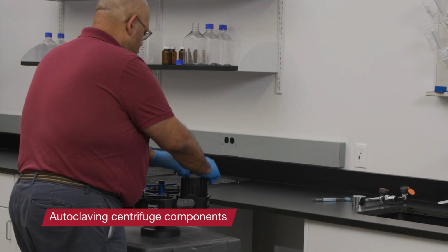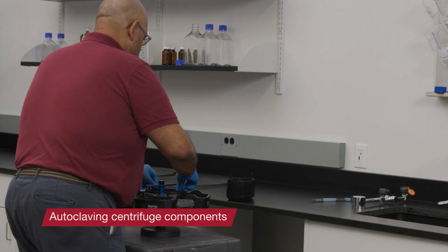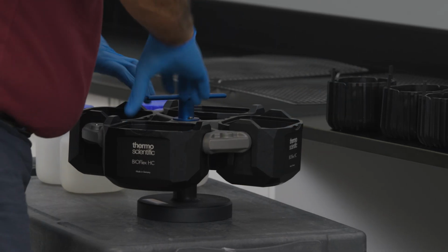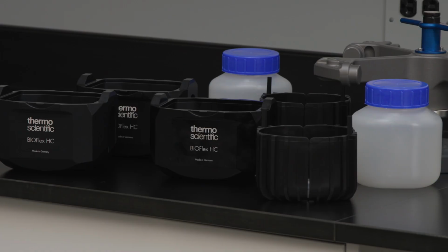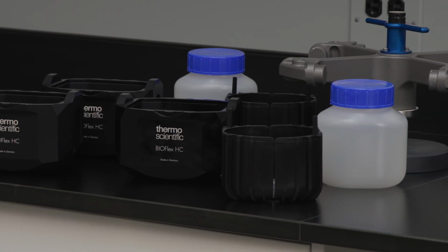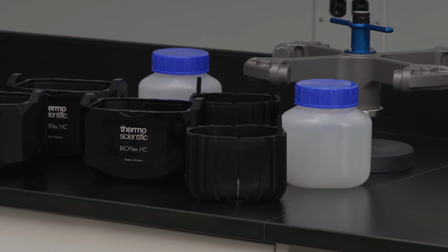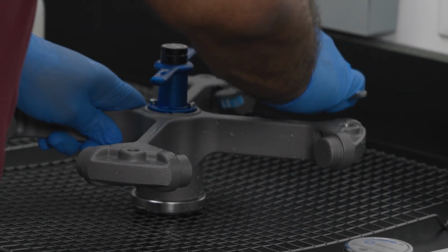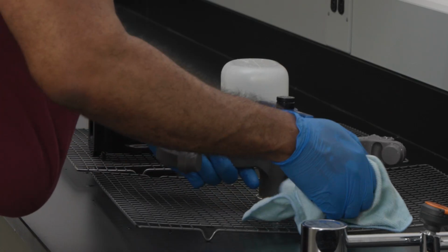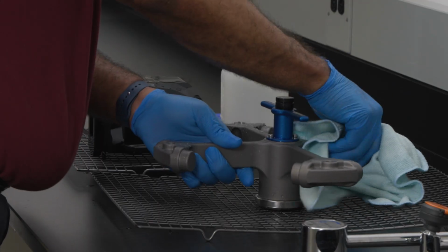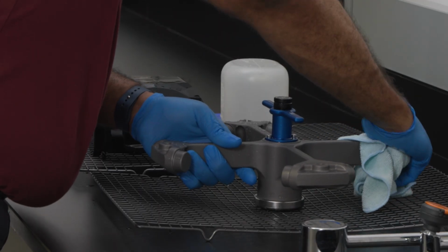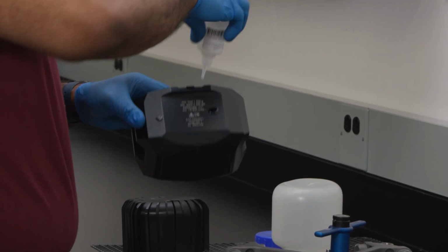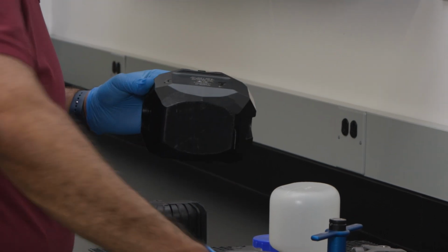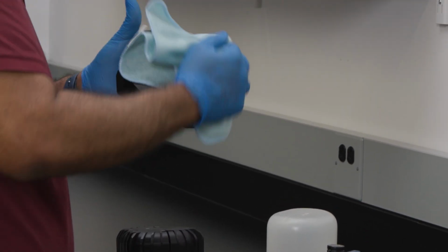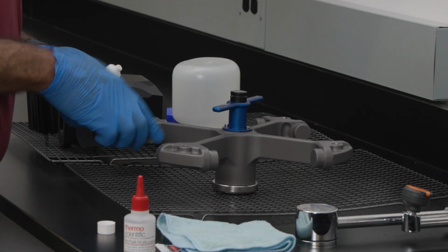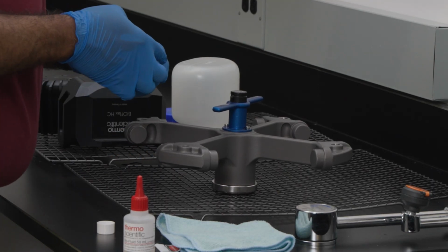To autoclave components, separate the rotor, buckets, lids, adapters, tubes, and sealing rings. If installed, remove lids from rotors, buckets, and tubes. Autoclave components at 121 degrees Celsius for 20 minutes. Do not add chemicals to the steam and never exceed the permitted temperature or duration. After autoclaving, treat aluminum parts and cavities with corrosion protection oil. Apply bolt grease to the trunnion bolts of the swing-out rotor.